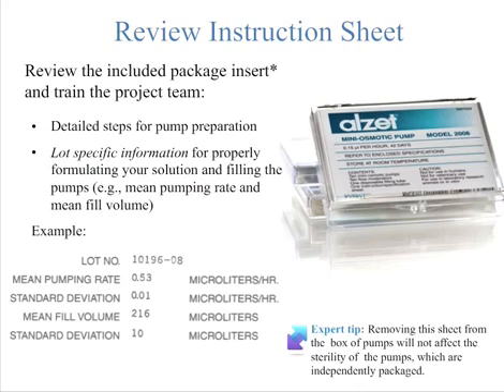And we do rigorous testing to find out what exactly these variations are. So, for example, for this particular lot of pumps, you'll find that the actual rate of infusion is 0.53 microliters per hour. And the actual mean fill volume is 216 microliters. The actual lot data listed in the instruction sheet is what should be taken into consideration when preparing your study and when formulating your solution.